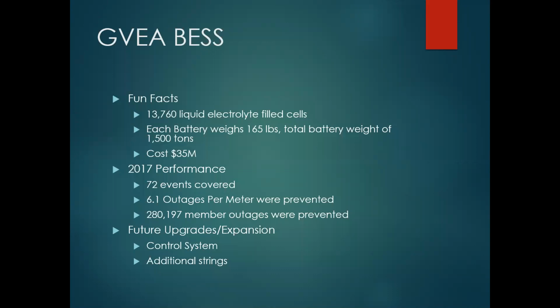And then in light of Healy Unit 2 coming online, we may be looking at adding additional strings. Originally the BES was sized so that we could cover close to 50 megawatts for 15 minutes from here in town. With Healy 2 not on, our transfer going from south to north is small enough that we can usually cover it with the current BES size.